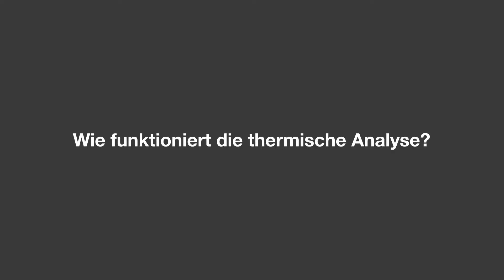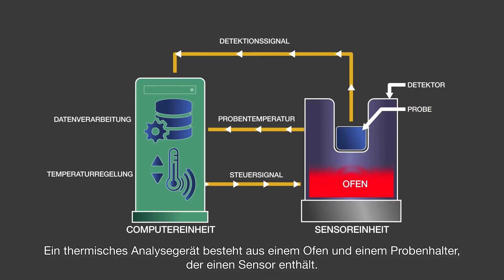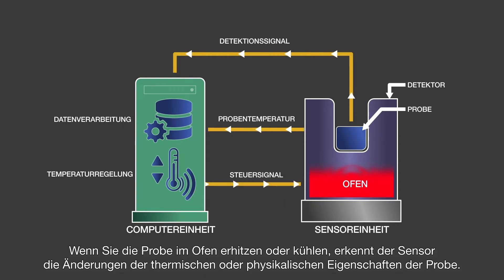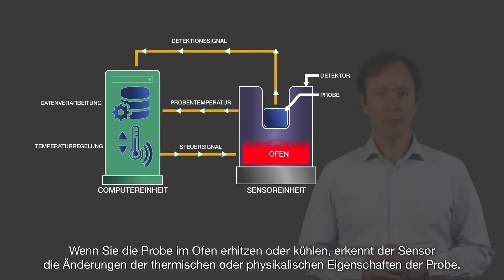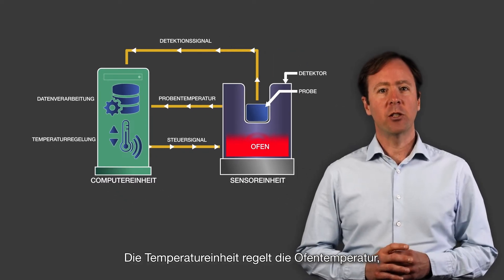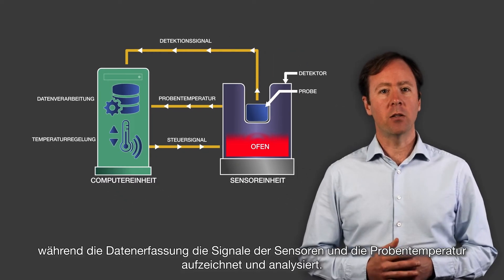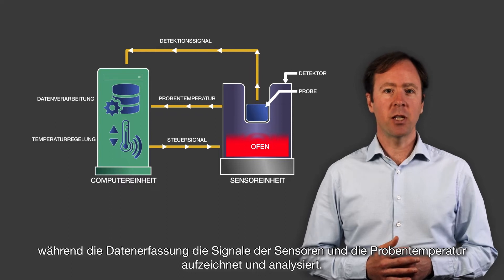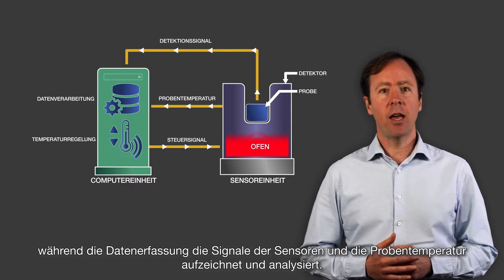How does thermal analysis work? A thermal analysis instrument consists of a furnace and a sample holder, which includes a sensor. As you either heat or cool the sample in the furnace, the sensor detects the changes in the sample's thermal or physical properties. The temperature control unit controls the furnace temperature, whilst the data recording unit records the signal of the sensors and sample temperature and analyzes them.